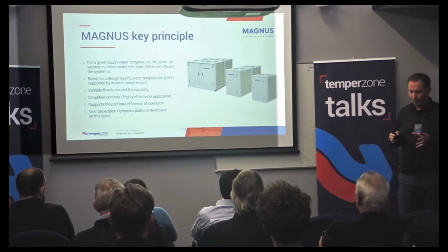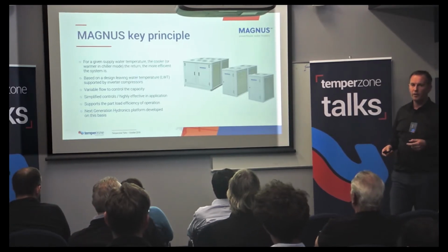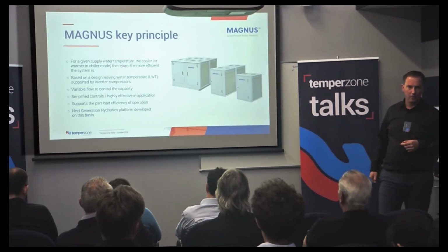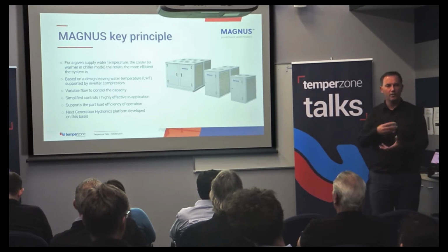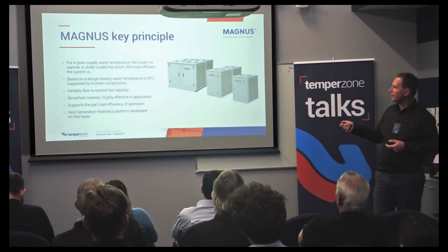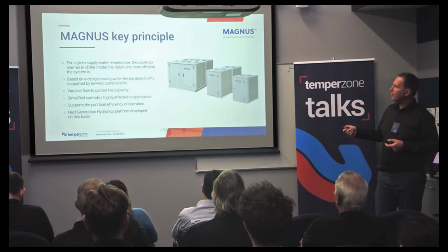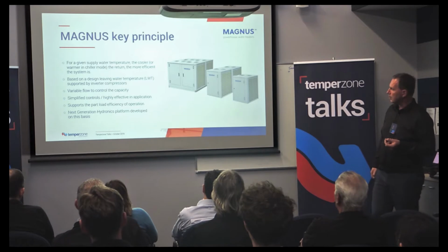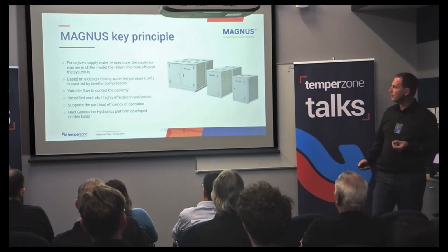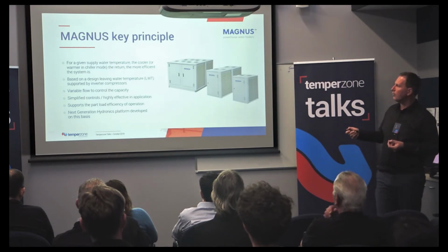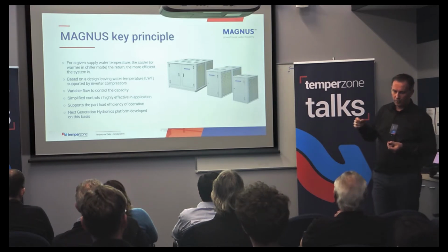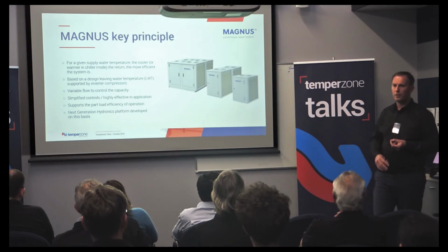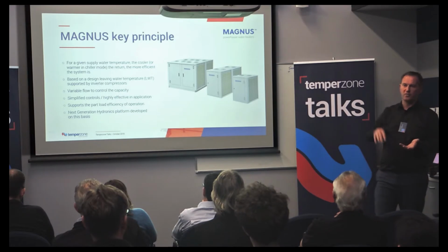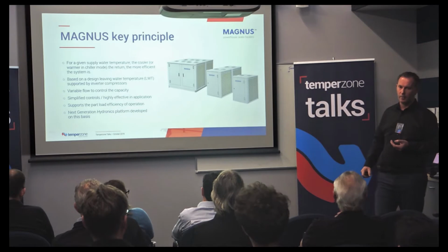The overriding principle is for a given supply water temperature, the colder or the warmer you can make the return water into it, the more efficient the system is. And the entire project is how you reconfigure both the unit and the application to take advantage of this principle. Very much based on inverter compressors, we're trying to drive that part load efficiency. The controls become very simple because all that we're mostly doing is changing the water flow. So instead of directly controlling the inverter like we used to with aircon, we can control the water flow. The compressor sees the change in water flow and what the return water temperature is, and it runs whatever speed it needs to meet the design leaving water temperature.